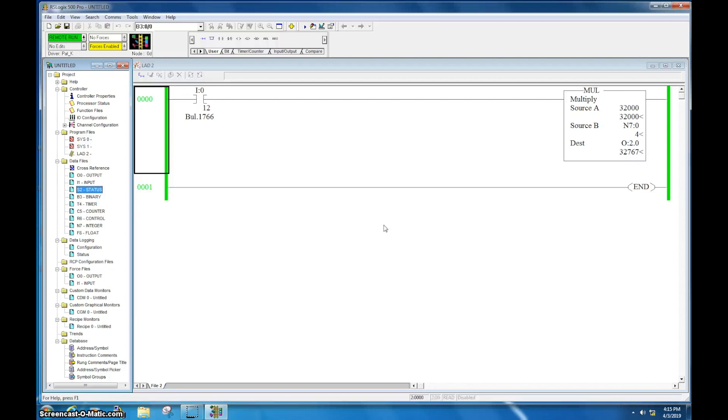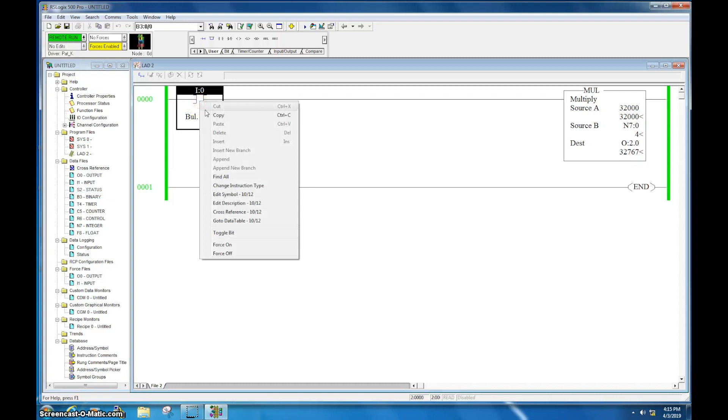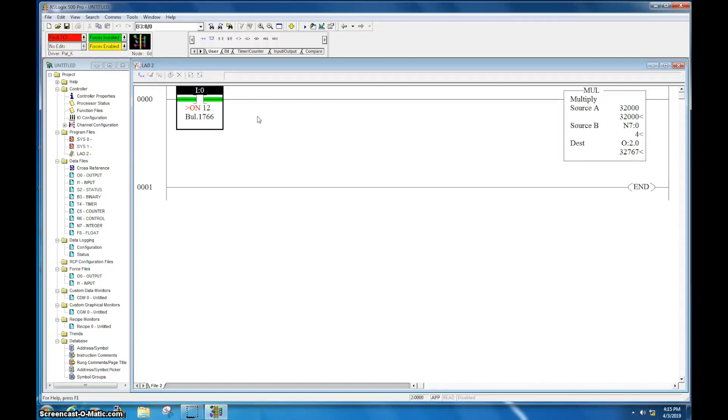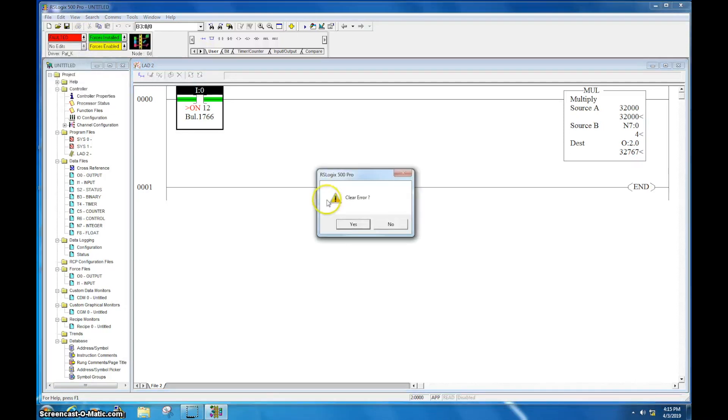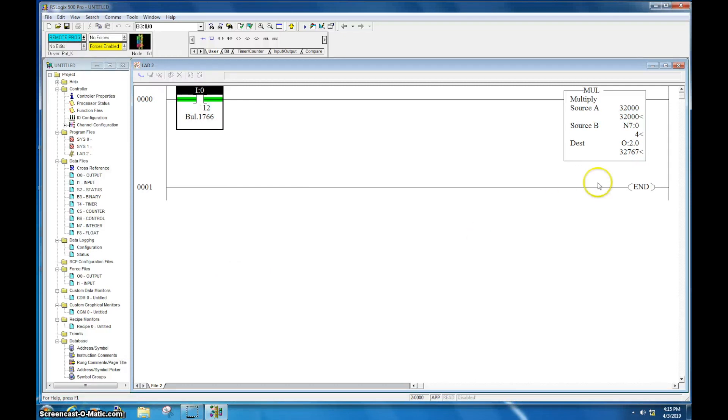Now the problem here is, if I come and activate this again, it will create a fault. I didn't solve the problem. So if this is just some one weird time occurrence that will never happen again, our steps are good. If not, I have to go in and fix the problem. So I'll come here, clear fault, hit yes, I'm going to remove my force.